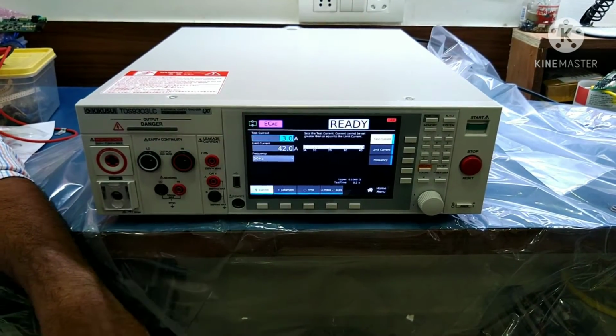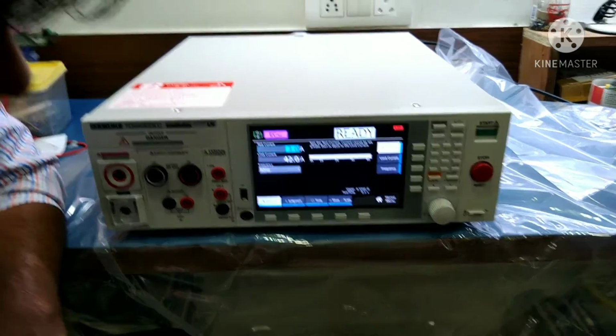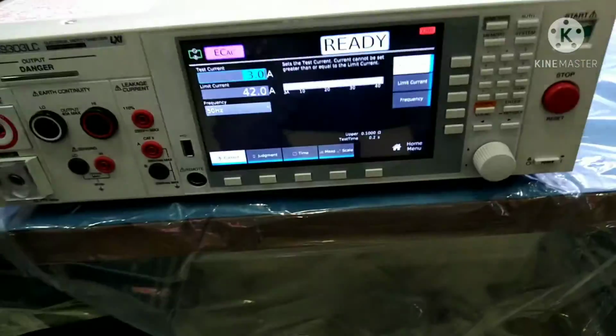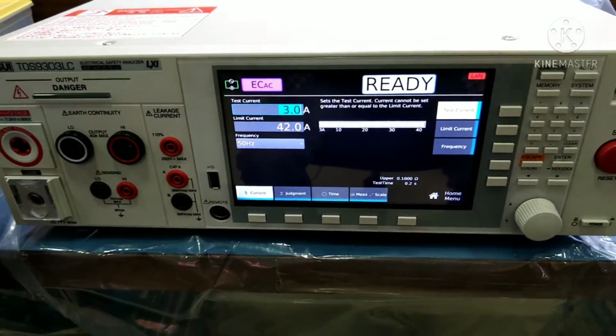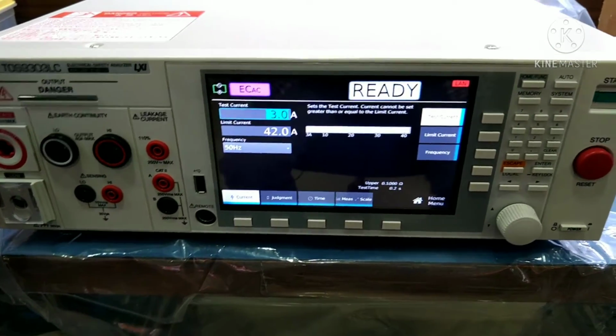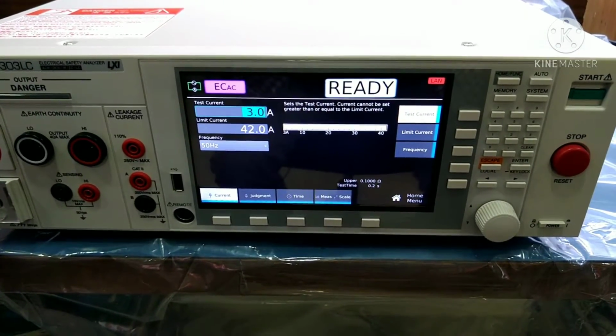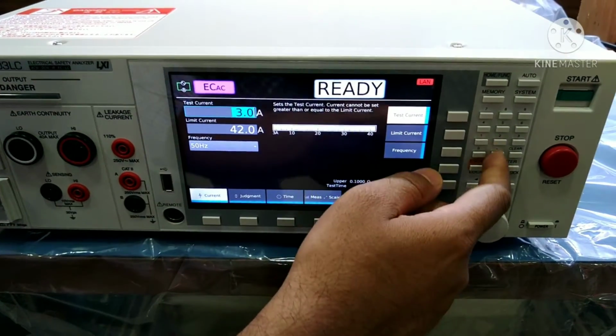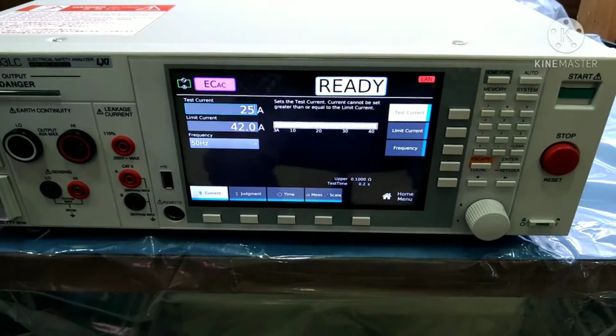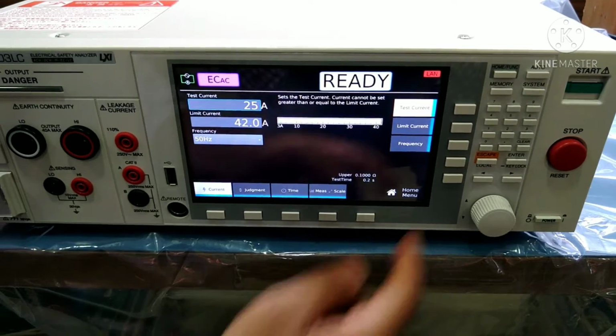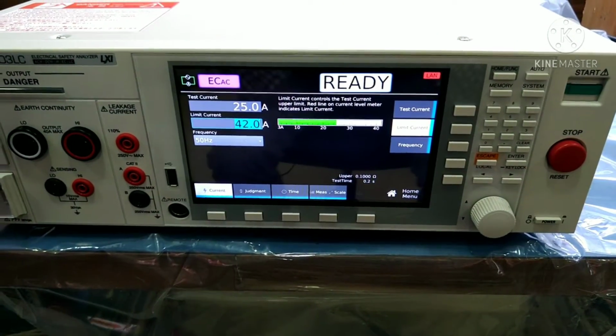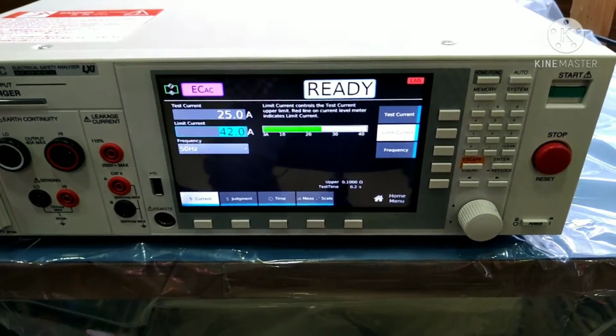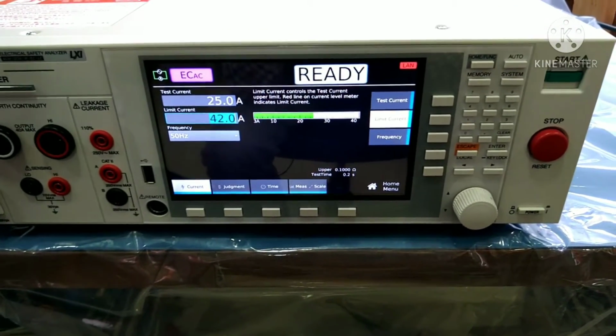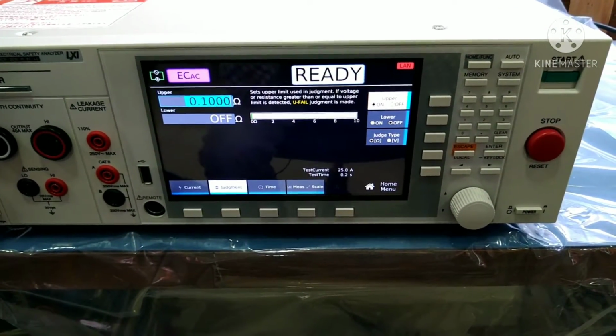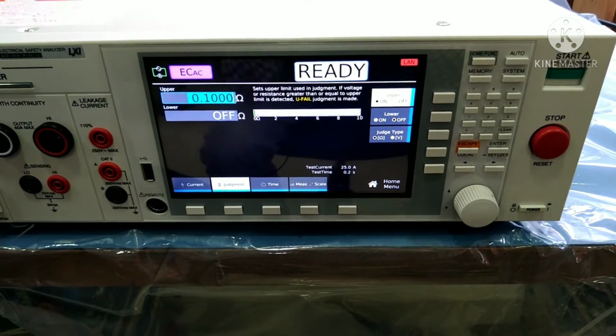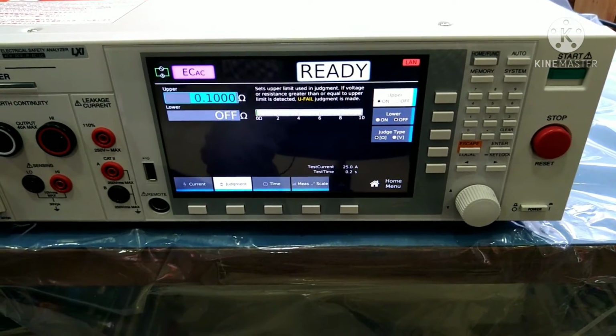Here you can set the maximum capacity up to 42 amperes, that is the maximum limit current. As per your testing parameters or testing standards, you can set the current here. Like I'm going to set 25 amps. The limit is the maximum limit, which we will not disturb. The judgment is there, so you can set the upper value for any product.